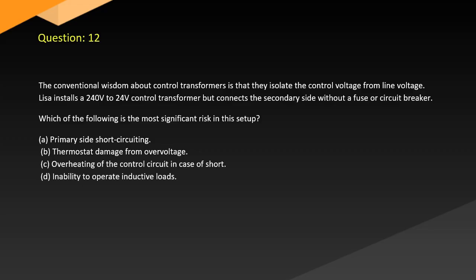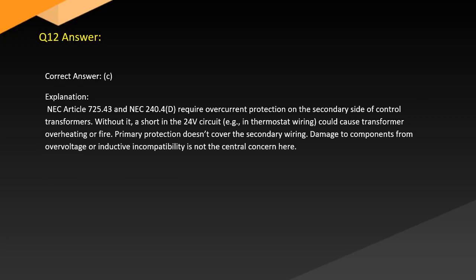C. Overheating of the control circuit in case of short. D. Inability to operate inductive loads. Answer. Correct answer: C. Explanation. NEC Article 725.43 and NEC 240.4(D) require overcurrent protection on the secondary side of control transformers.